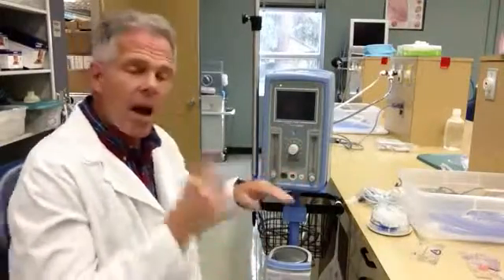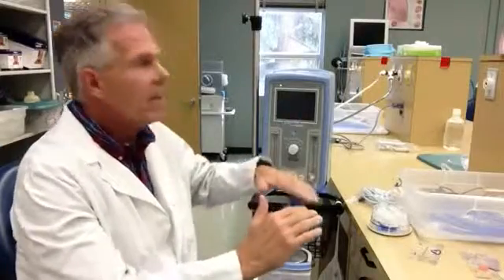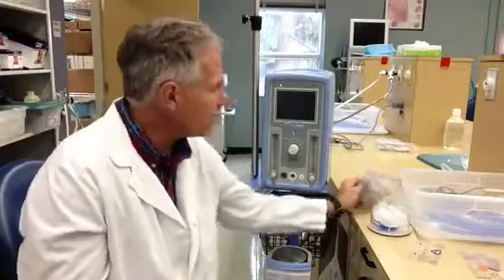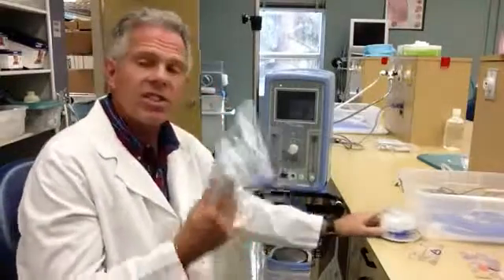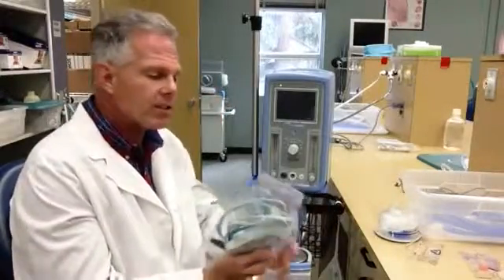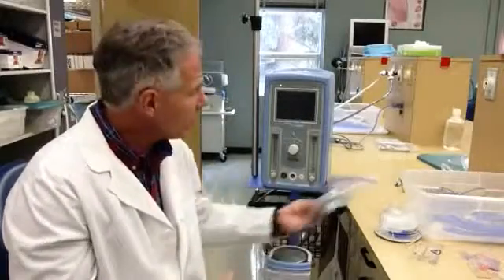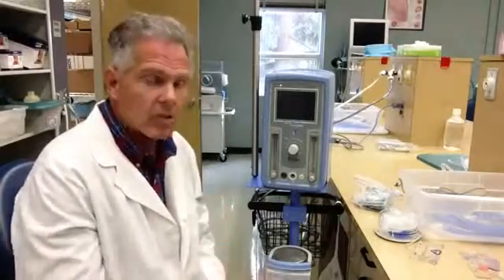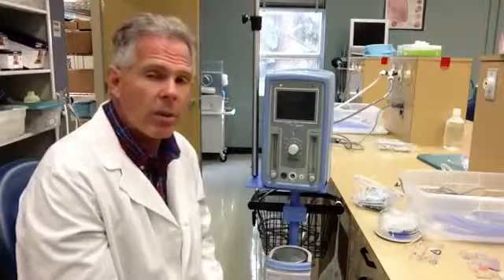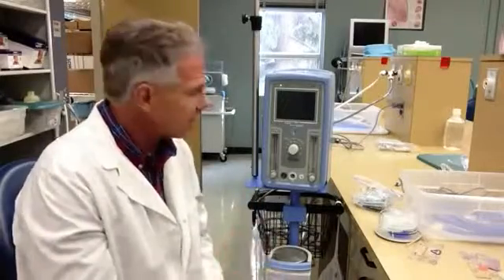It can be used as an IMV device, which means it can give intermittent mandatory ventilation. It does have the ability with a special sensor to synchronize with the baby's inspiratory efforts, but this hasn't seen a lot of clinical use. Its primary use is to deliver nasal CPAP or continuous positive airway pressure. So let me show you how that's set up.